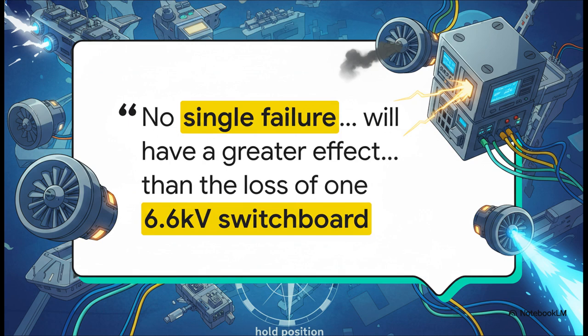So the absolutely foundational concept here is the worst-case failure design intent, or WCFDI. The rule is incredibly strict. Even if we completely lose a 6.6 kilovolt main switchboard and, say, 3 thrusters go down with it, we must hold our position. That is the absolute baseline standard for all of our trials.